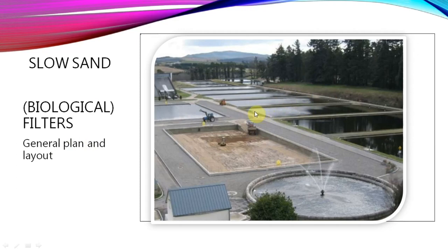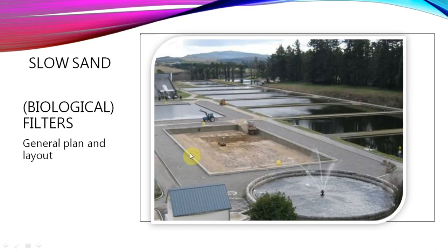Slow sand or biological filters need a very large area, as you can see from the pictures. Each filter bed, after a few weeks, becomes less efficient. We need to remove the top layer of sand and replace it with new sand, then wait one to two weeks for the biological zooglial layer to reform. Since we can't stop the water supply, we need many similar plants running simultaneously. This requires very large land area, unlike rapid sand filters.